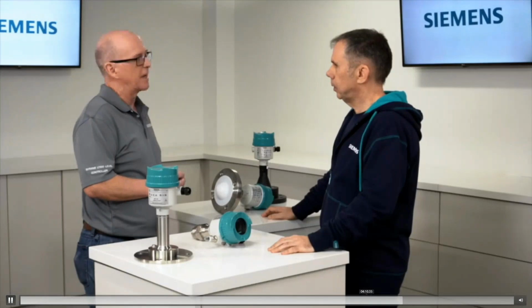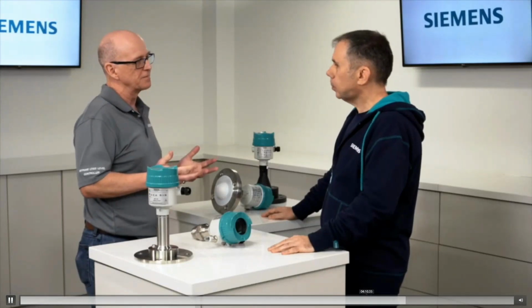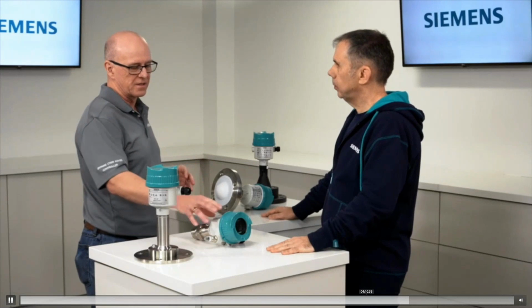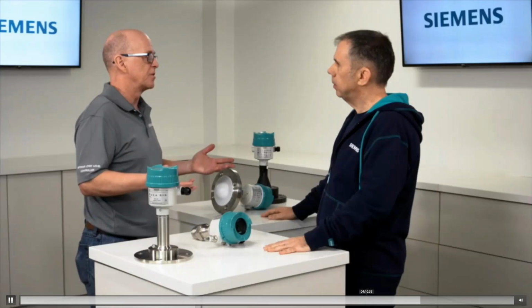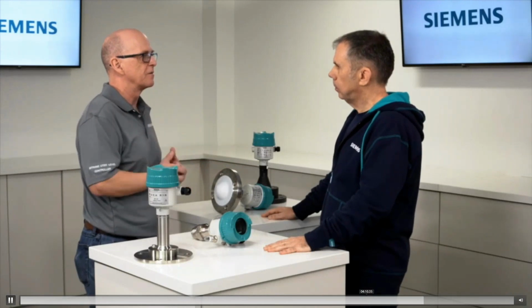In addition, have we made any improvements or changes to our process intelligence? Yeah, good question. We've got, of course, process intelligence in these new advanced radar series. In addition to that, we've got near-range suppression. It's a new feature, and what this does, Mark, is it continually monitors and evaluates and removes the noise caused by antenna buildup or nozzle buildup that would traditionally cause a false high level and false readings.